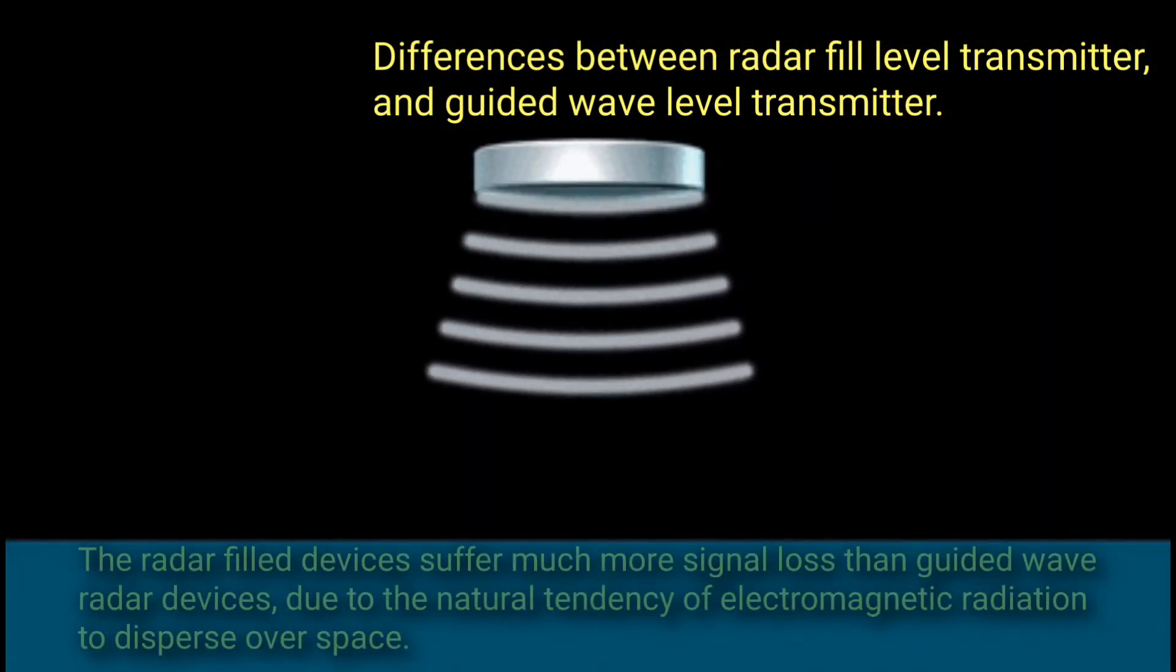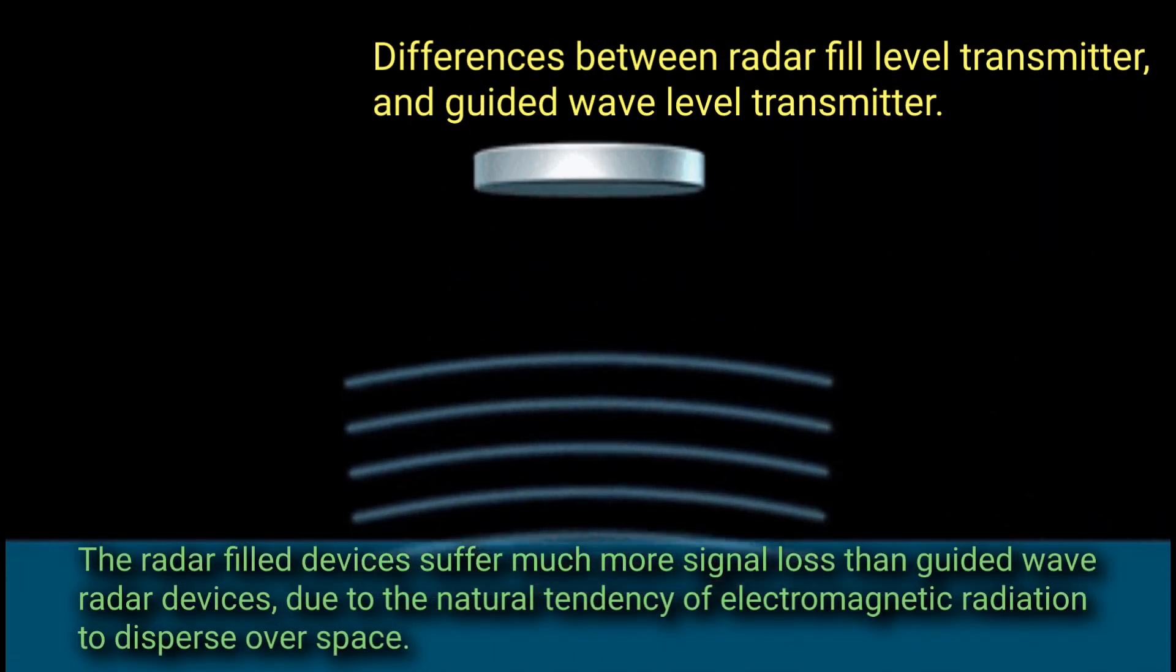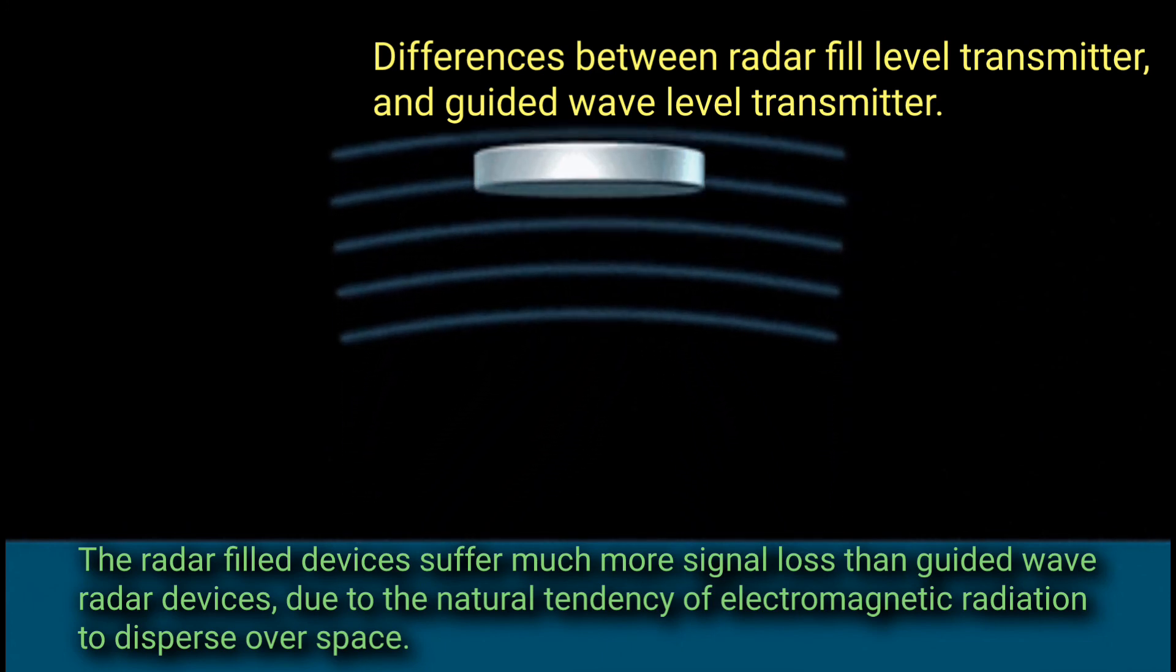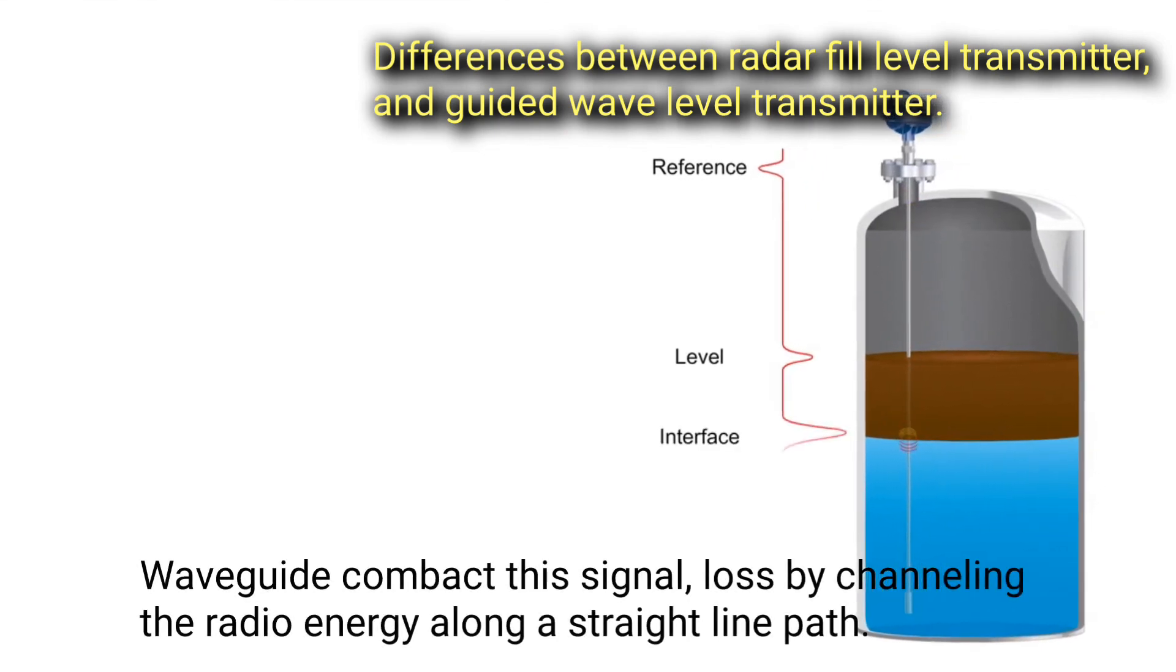The radar fill device suffers much more signal loss than guided wave radar devices due to the natural tendency of electromagnetic radiation to disperse over space. Waveguides combat this signal loss by channeling the radio energy along a straight line path.